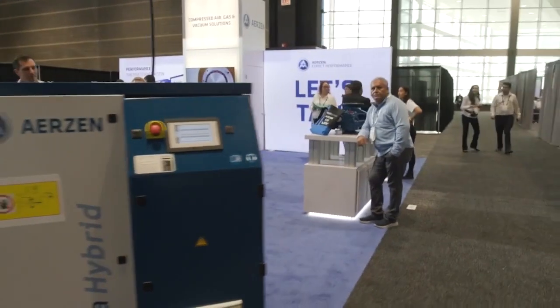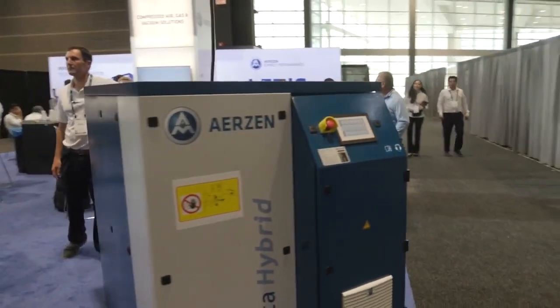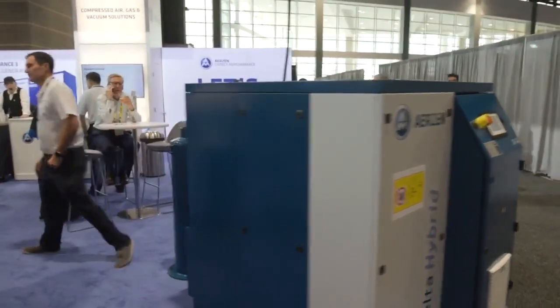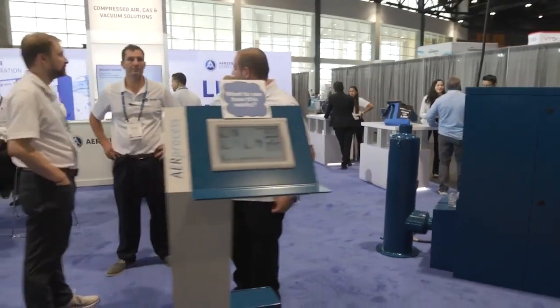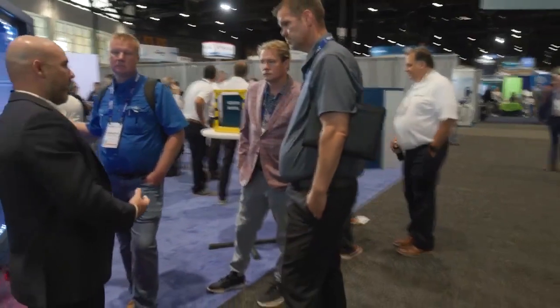What you'll really find in the majority of the rental industry is what we call plant air compressors that are capable of compressing air up to 100 pounds. And when they're applied in the wastewater industry, it's a lot of wasted energy. In a wastewater plant, you're going to have a blower and you're going to have the installed electrical service to supply that blower, which is not necessarily capable of supplying the power to a plant air compressor.